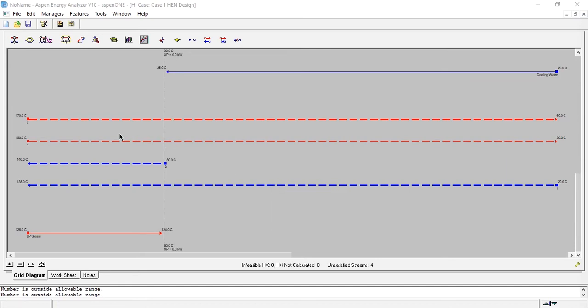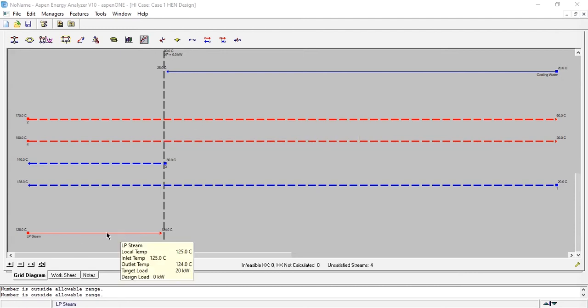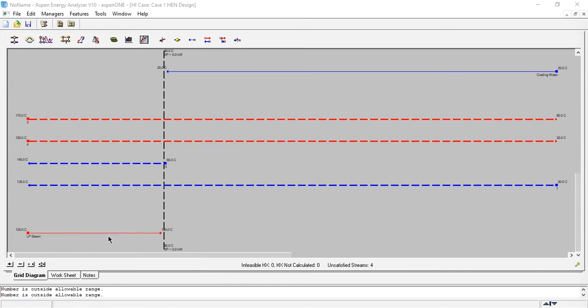The rule is satisfied. For above pinch, the number of hot streams should be less than or equal to the number of cold streams — two and two, satisfied. For below pinch, the number of hot streams should be greater than or equal to cold streams — two hot, one cold, satisfied. We also check CP values: CP of hot stream should be less than or equal to CP of cold stream above pinch, and the opposite below pinch. LP steam is the heating utility, cooling water is the cold utility. The golden rules: hot utility can only be used above pinch, cold utility only below pinch, and no heat transfer across the pinch.